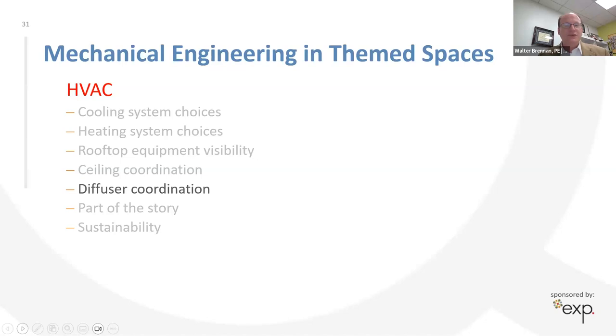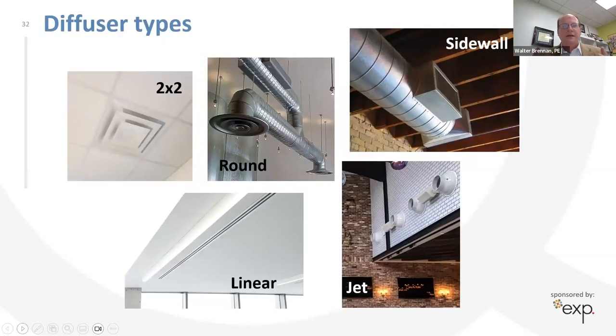Another topic has to do with diffuser coordination. Diffusers are how the heated or cooled air actually gets into the space, and there are lots of different options. You've seen it in your classroom or office space - those square 2x2 diffusers on the left. If you don't have ceilings, you probably see the round ones in the middle. We also have sidewall diffusers. One we use a lot in the entertainment industry is the linear diffuser in the lower left corner - it allows us to hide the air much more easily than the other three. Then there's the jet diffuser, which is my favorite because it looks epically cool in a space.